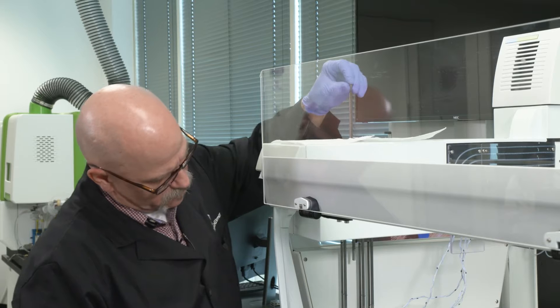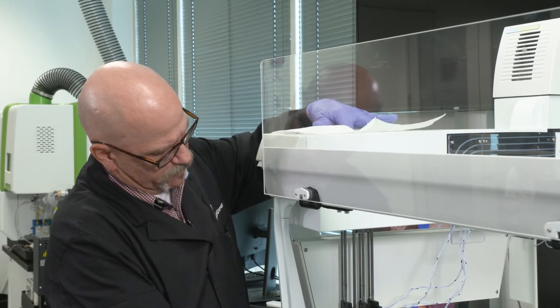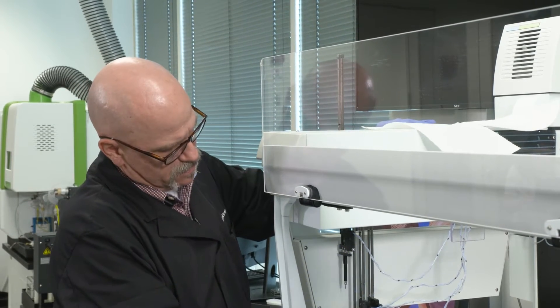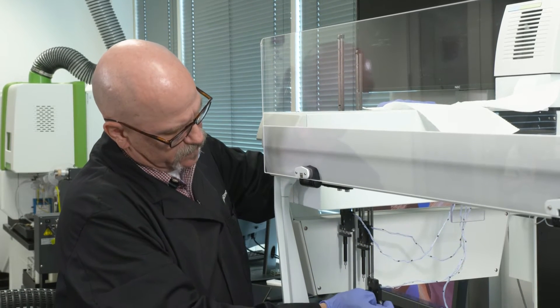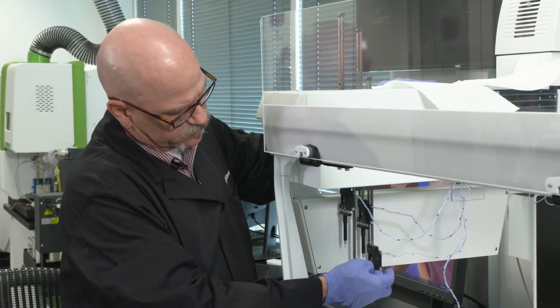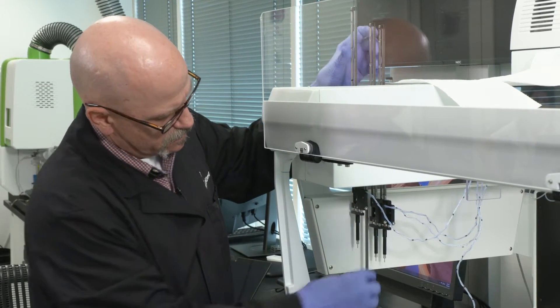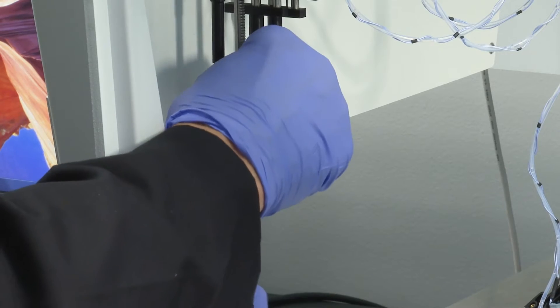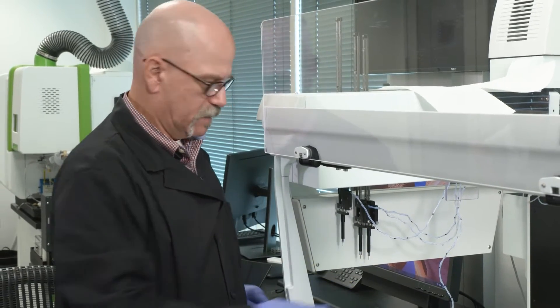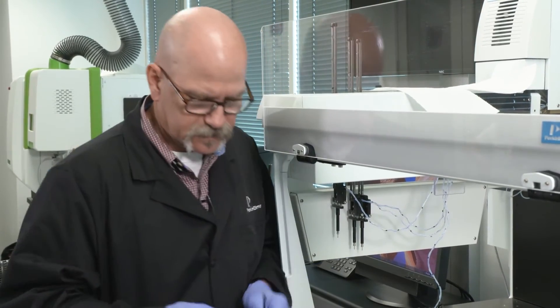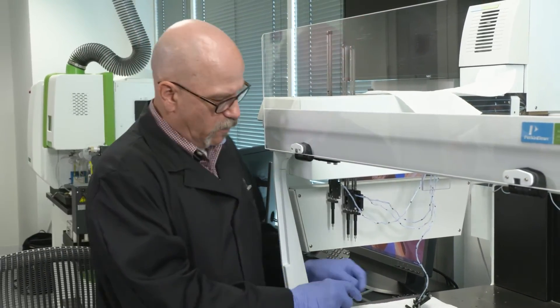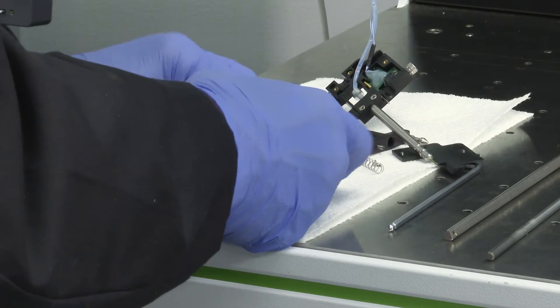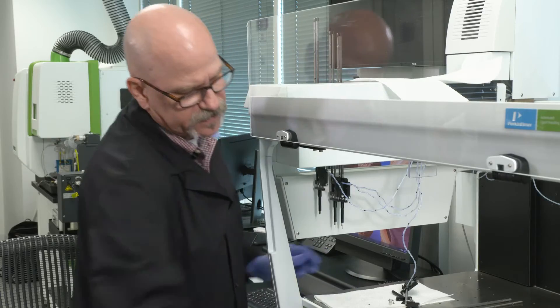Once we've done that, we push back down on the Z-Rack and we're going to push up on the tip housings of the others. Note that I always push up on the solid part of the tip housing, not on the tip stripper sleeve. And we remove the bent Z-Rack. Now we're going to remove the clip over the paper towel to make sure that we don't lose it. By pushing on each end of the clip, it comes off fairly easy. So we'll set these used pieces aside.